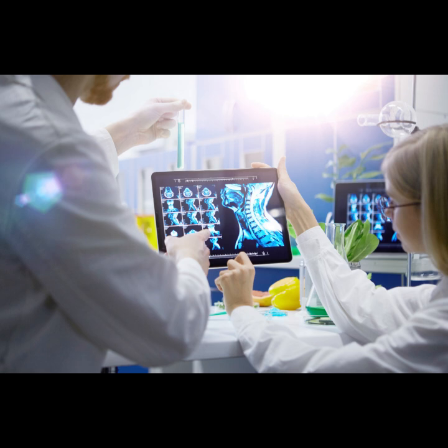Exactly. No magnet is perfect. Plus, the patient's own body distorts the field slightly. So even within the same tissue type, spins in slightly different locations will experience slightly different local magnetic fields. And therefore precess at slightly different speeds, even without a gradient. Precisely. This causes them to dephase and the signal to decay faster than it should, based purely on the tissue's intrinsic properties. This extra decay rate is what we call T2*. So T2* is always shorter than the true intrinsic T2.